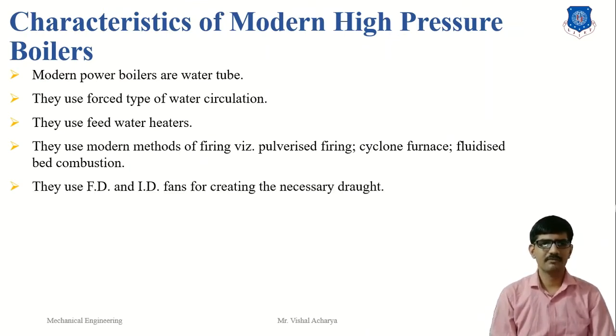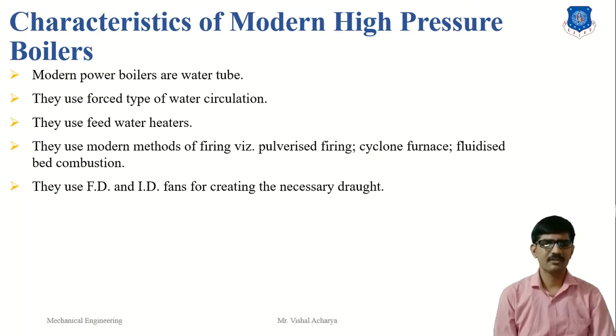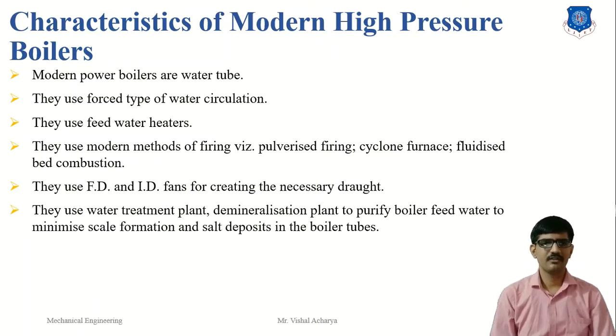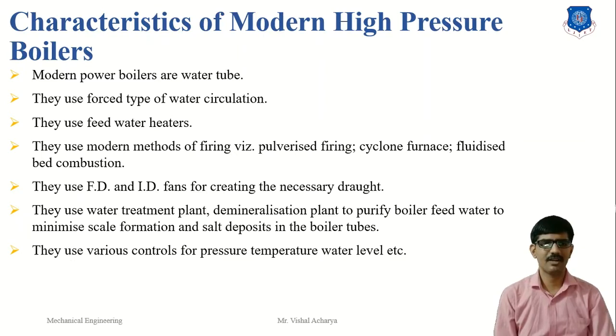They use FD and ID fans — meaning forced draft and induced draft fans — for creating the necessary draft. So the circulation of the air and the exhausting of flue gases is very efficiently managed. Feed water treatment is used so that the corrosion of the boiler is prevented by the use of the feed water treatment plant.